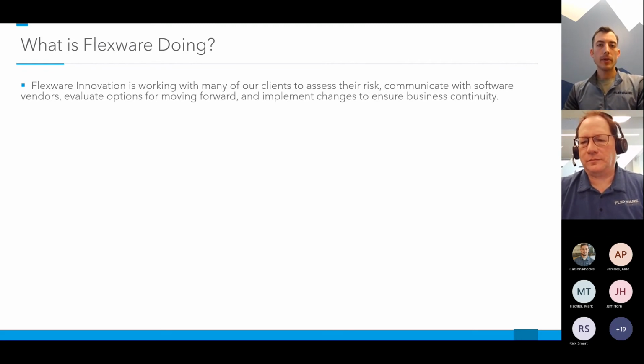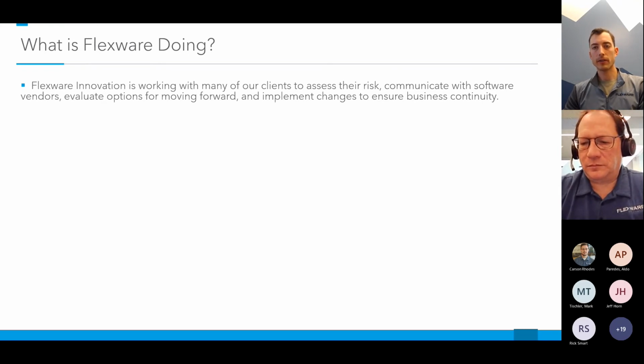Yes, so legacy OPC DA is affected by DCOM hardening and distributed architectures. Again, with the client and server being on different machines, they would use DCOM to communicate. And so if they're not at the same authentication level, then yes, there would be issues. Again, there's this November 8th patch from Microsoft that might alleviate that. So I encourage you to use that patch and do testing offline as much as you can.